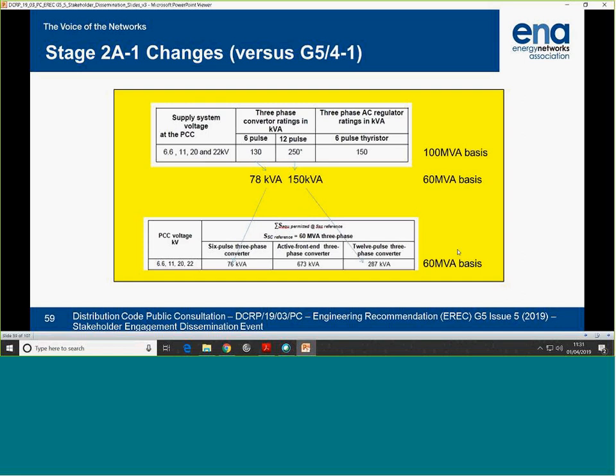To convert the old values to the new, you have to check the basis of them, and that's what that middle line is. Six pulse was 130 on a 100 MVA basis. That becomes 78 on a 60 MVA basis, and that compares with 76 in the new values. 12 pulse converts to 150, and that compares with 287, so that's a bit higher. And now you've got active front-end converters in there as well, but you've lost the regulator part, the 3-phase AC regulator part.